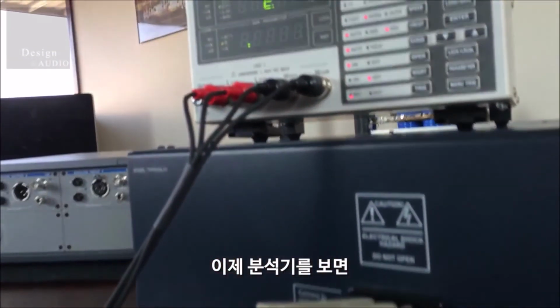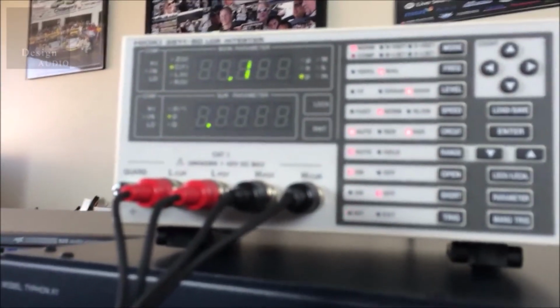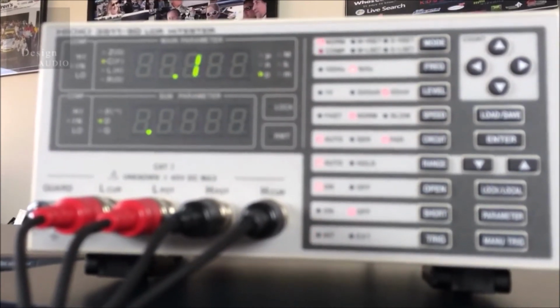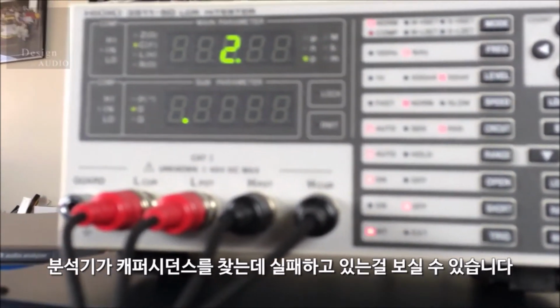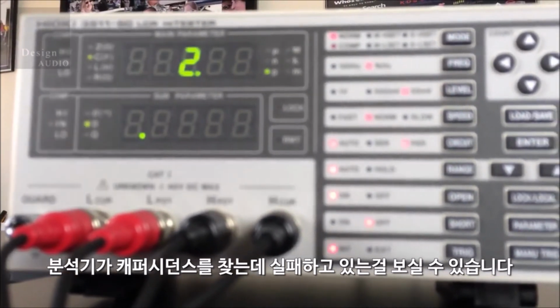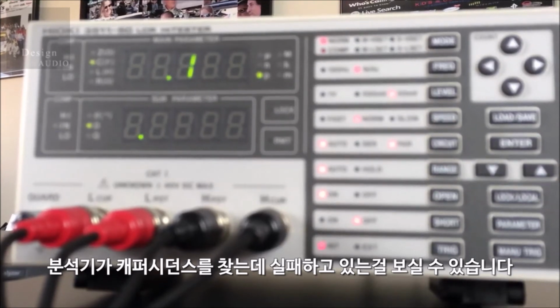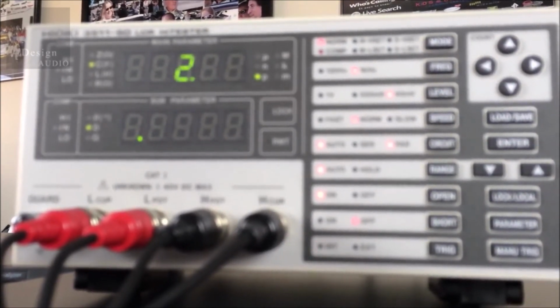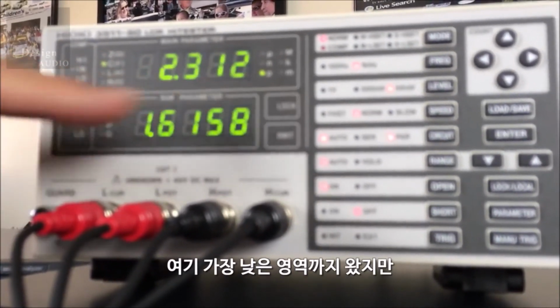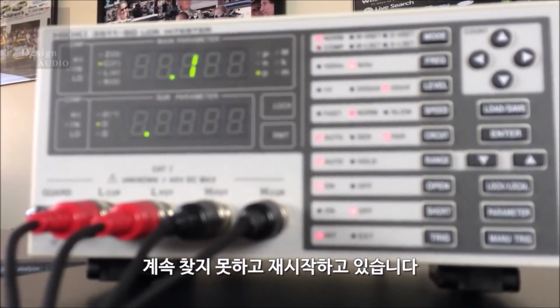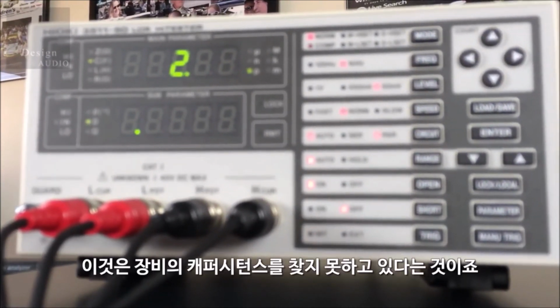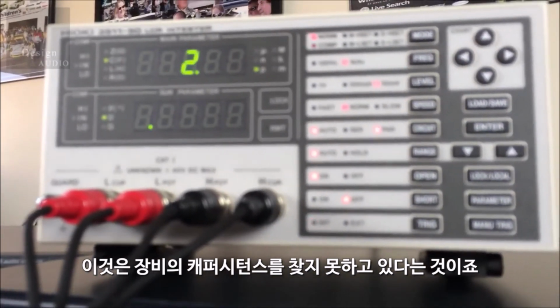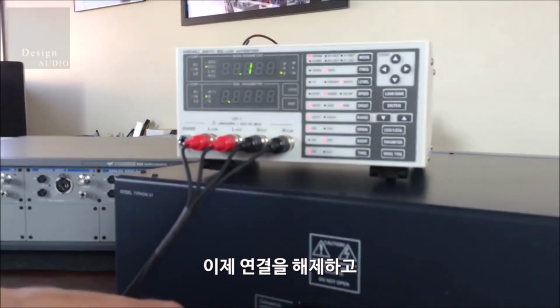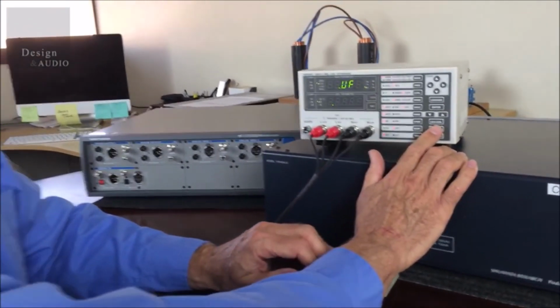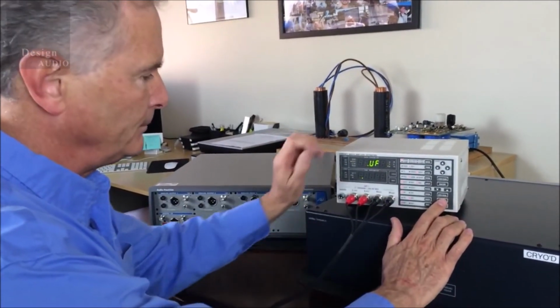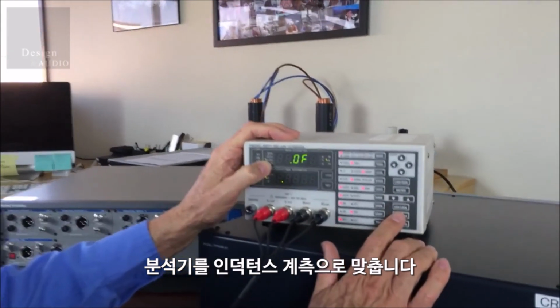Now if you look at the display, you can see that the analyzer's searching. It's trying to find a capacitance reading, and it's having trouble doing that. So right now it's looking down in the picofarad range, which is very low. And as you can see, it keeps searching, gets confused, and starts all over. This indicates that it can't find any capacitive reactance of the unit. Now what we're going to do is we're going to disconnect it, and I'm going to change to inductance reading.